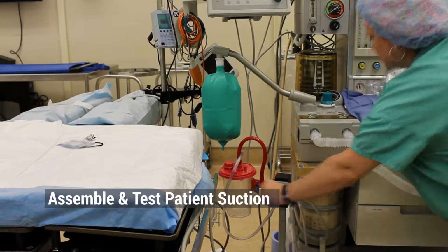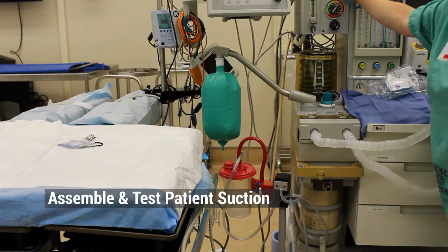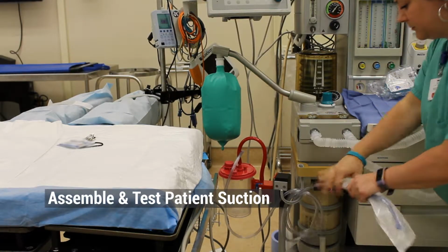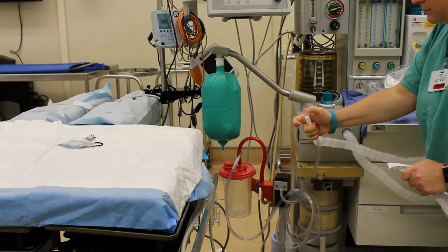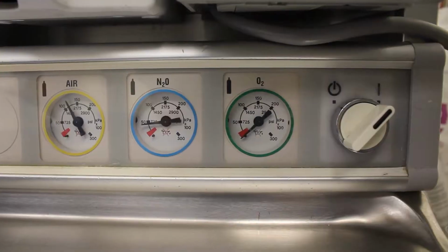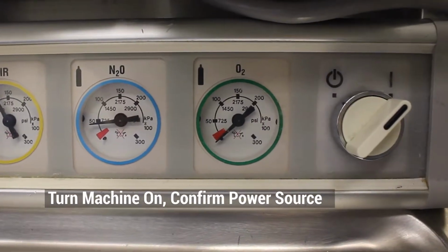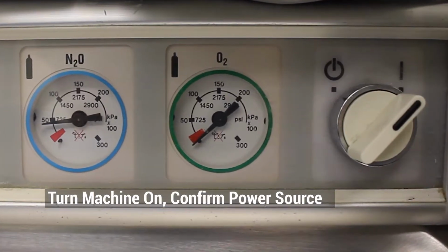Verify that patient suction is set up and producing adequate suction to clear the airway. Turn the anesthesia machine on and confirm that it is running on AC power. If the machine is already on, turn it off and then back on again in order to perform startup self-checks.